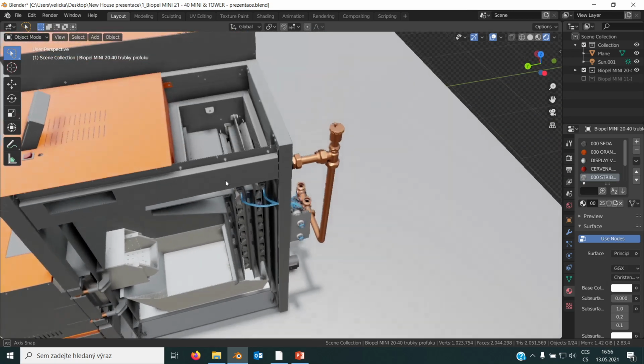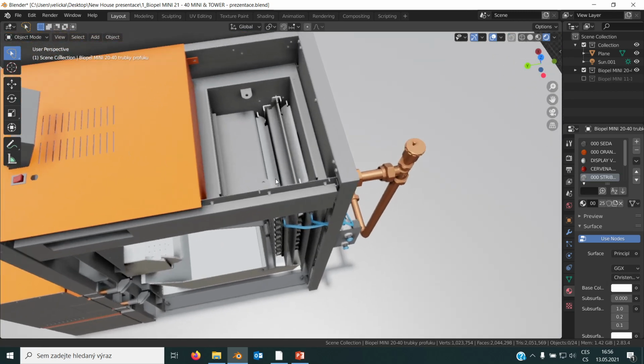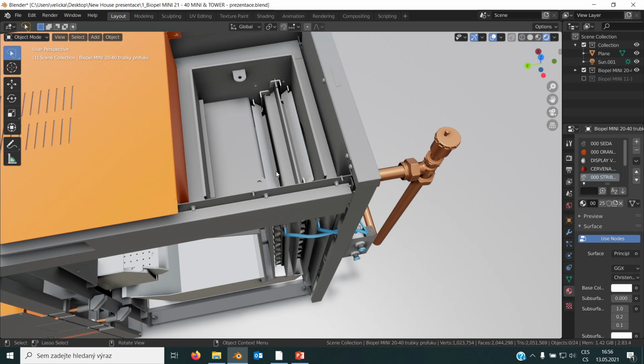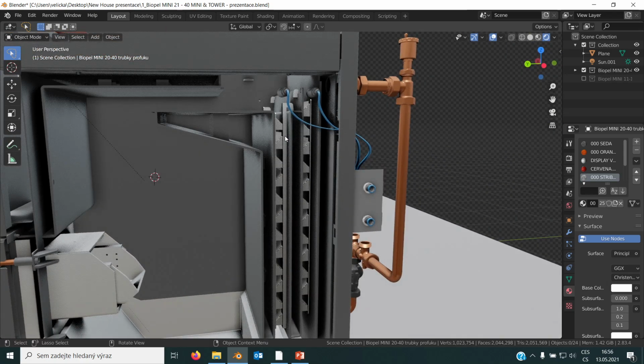And because the heat exchanger itself is 50% smaller compared to V9 Premium, the efficiency of the cleaning is really high. So it is really simple, easy to clean, and it is efficient. Of course, it depends on the quality of the combustion, quality of the pellets, but if the ashes are dry, if the combustion is good, for example, with our 15 kilowatt Biopel Mini boiler in our boiler room, we didn't clean the heat exchanger for 6 months with this compressor cleaning.